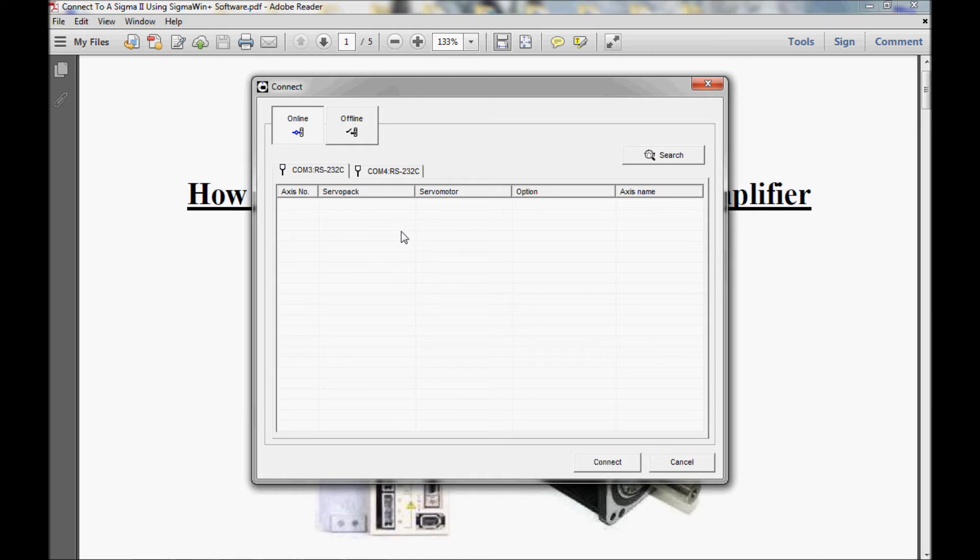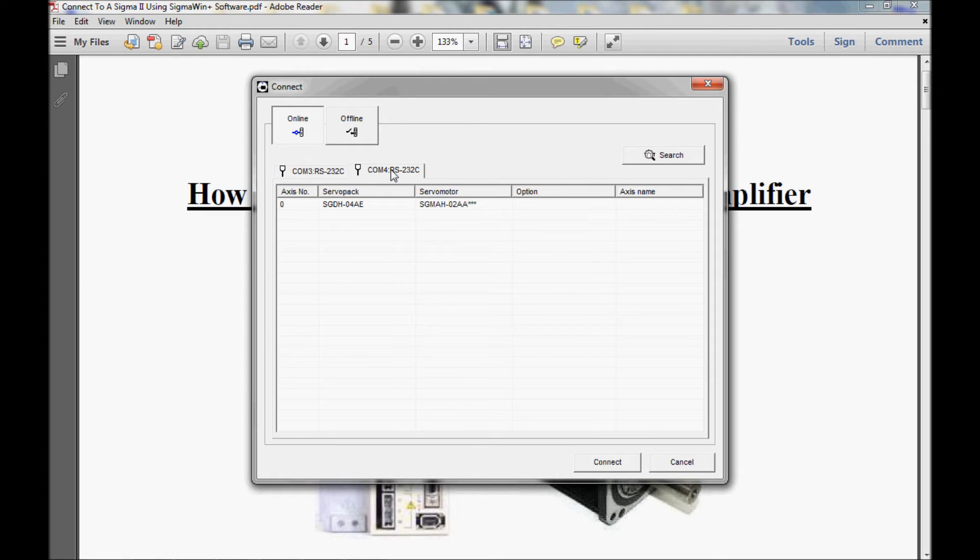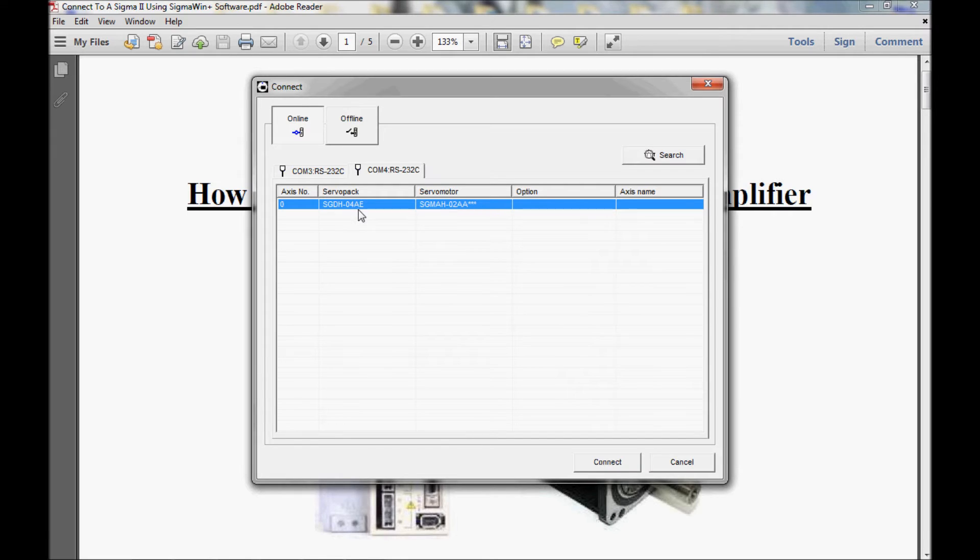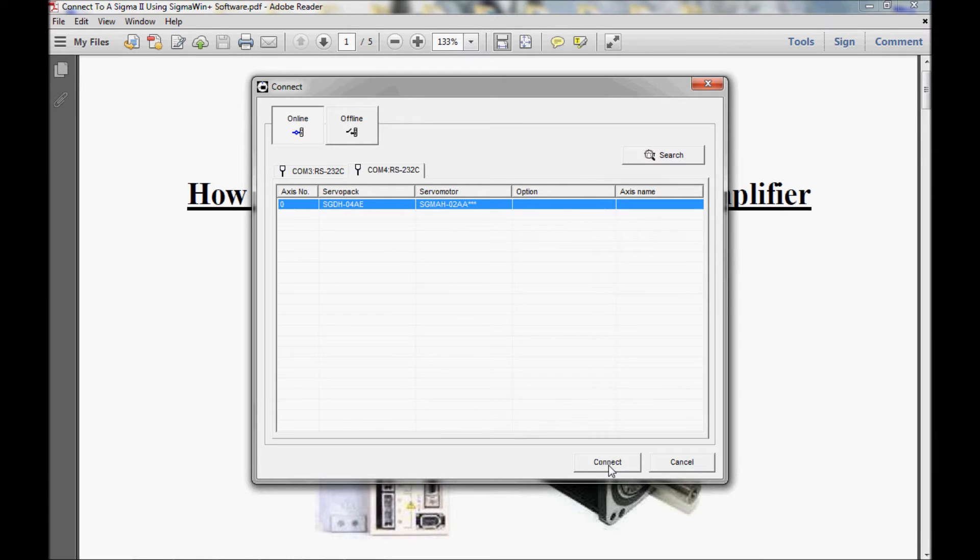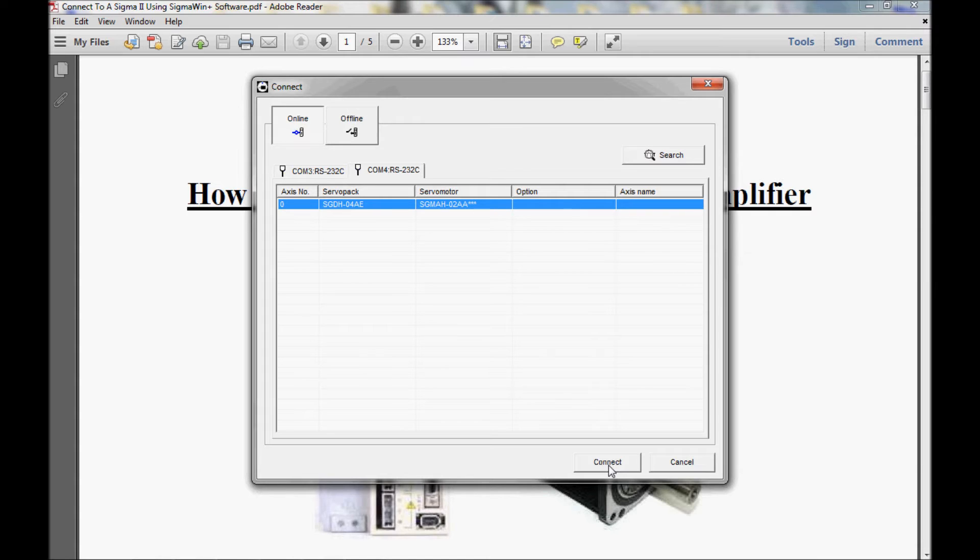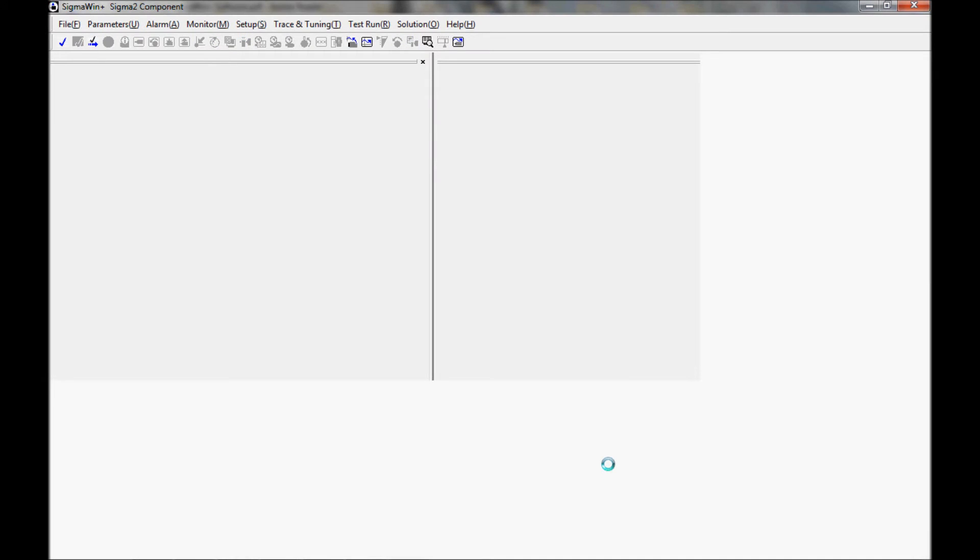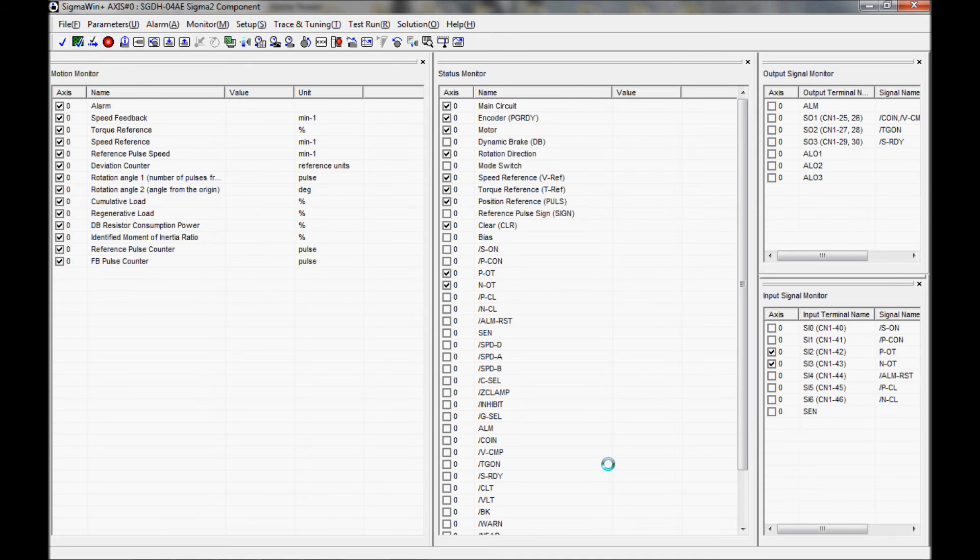You can see it reduced the amount of addresses it looked through. I did not get an alarm, but I do not see my amplifier located under the servo pack. But if you remember, I said I was using COM port 4. So let me click on the tab for COM 4. And there it is. So what I need to do is come down here and highlight the servo pack. I could have several servo packs here, but today I only have one. I am going to click on connect. You will see another screen pop up and give indication that it is searching. But on my servo pack, the display will go to black and remain in that state until either the cable is disconnected or I exit the program.